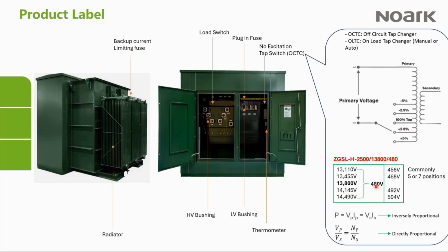Remember what I said about the relationship. If the voltage is reducing on the secondary side, then the current is going up, right? So that's how you know. Now, sometimes, because of seasonal usage, because of peak hour usage, the voltage that is expected at the primary can change. It can go up, it can go down. And because we want to have that same 480 volts, or as close as possible to 480 volts, on the secondary side, then we use this. That's why we need a tap changer.